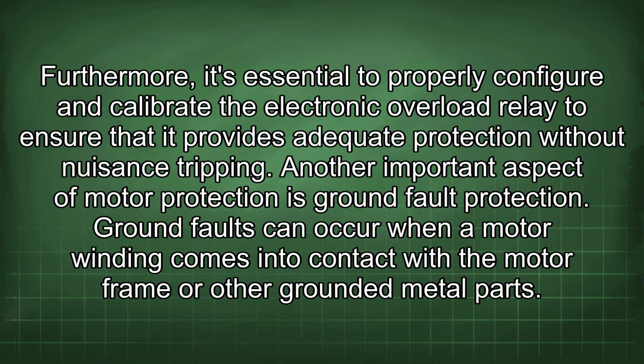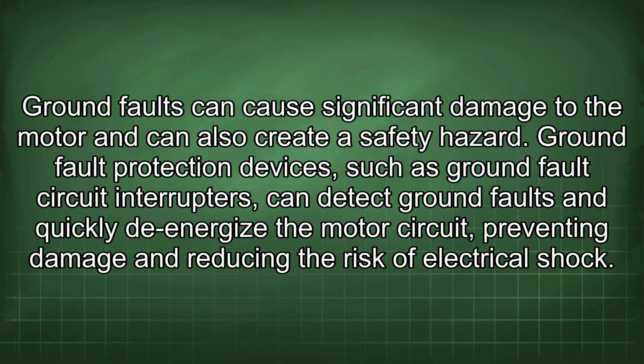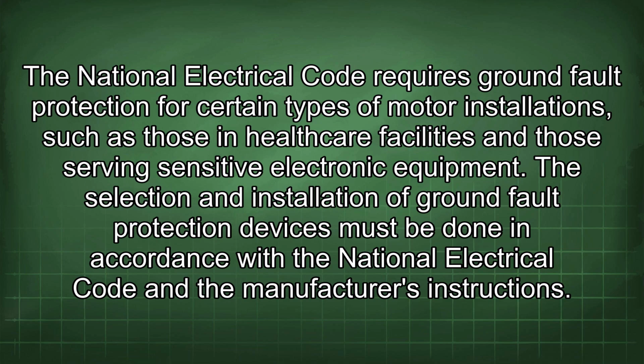Ground faults can occur when a motor winding comes into contact with the motor frame or other grounded metal parts. Ground faults can cause significant damage to the motor and can also create a safety hazard. Ground fault protection devices such as ground fault circuit interrupters can detect ground faults and quickly de-energize the motor circuit, preventing damage and reducing the risk of electrical shock. The National Electrical Code requires ground fault protection for certain types of motor installations, such as those in healthcare facilities and those serving sensitive electronic equipment. The selection and installation of ground fault protection devices must be done in accordance with the National Electrical Code and the manufacturer's instructions.